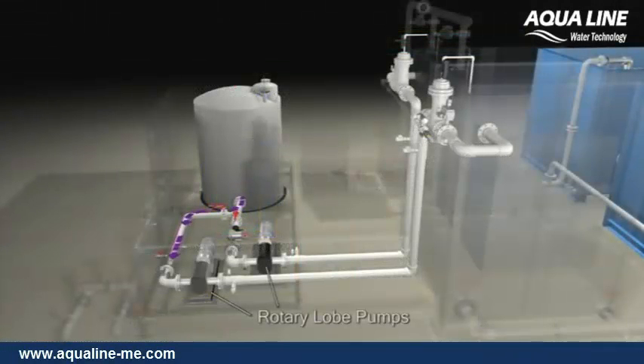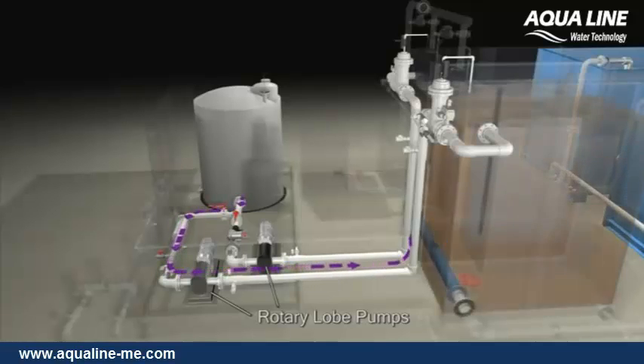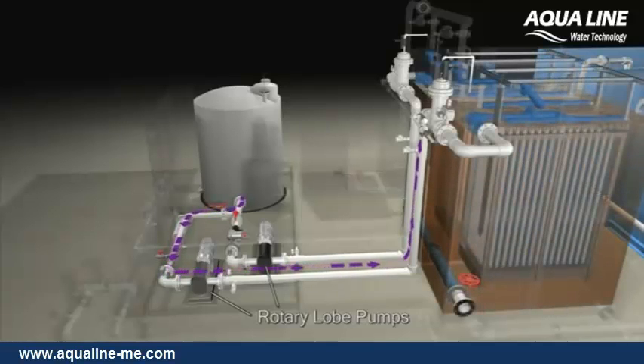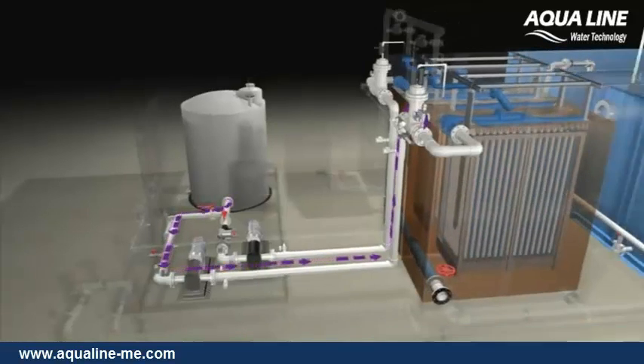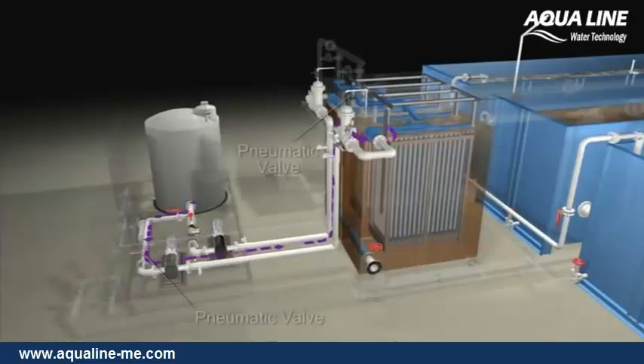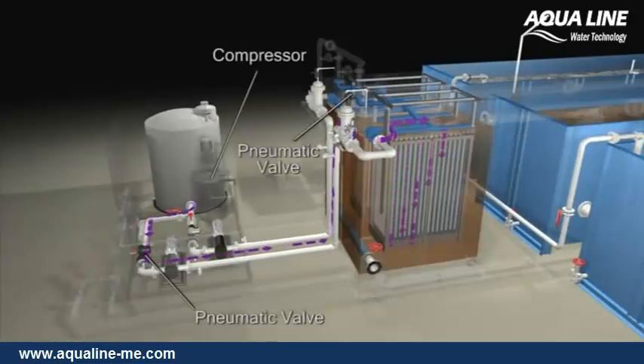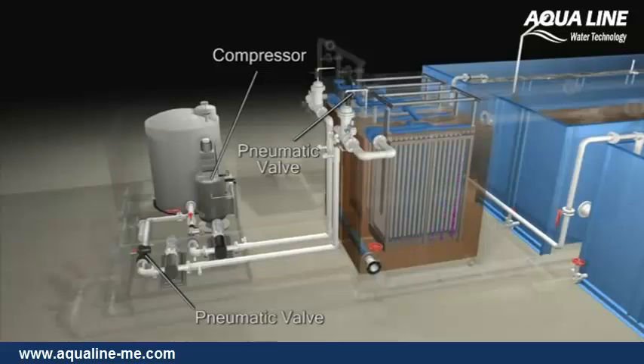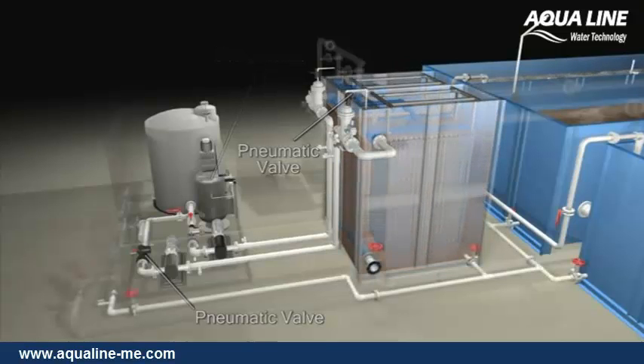The rotary lobe pumps periodically reverse the flow at predetermined frequencies and durations to back flush the membrane fibers. Pneumatic valves as well as pressure and flow measuring instruments provide continuous monitoring and control of system operation.